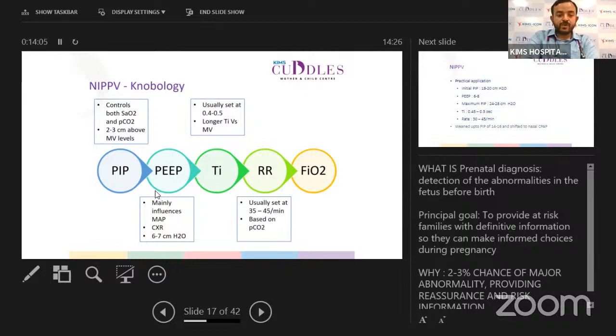Setting PEEP is important in mainly influencing the mean airway pressure, and it is titrated based upon the respiratory distress noted in the baby and the inflation seen on chest X-ray. The routine PEEP used during initiation of NIPPV is 6 to 7 centimeters of water. TI is usually set at 0.4 to 0.5 seconds. It is longer than what is used in conventional mechanical ventilation. Longer TIs are used because of the higher leak of inspiratory gases seen in NIPPV when compared to mechanical ventilation. Respiratory rate is usually set at 35 to 45, and higher rates are in general avoided because of the increased leak and to provide sufficient time for each respiratory cycle. It is also titrated based on the PCO2 levels. FiO2 is titrated based on the saturations noted in the baby.